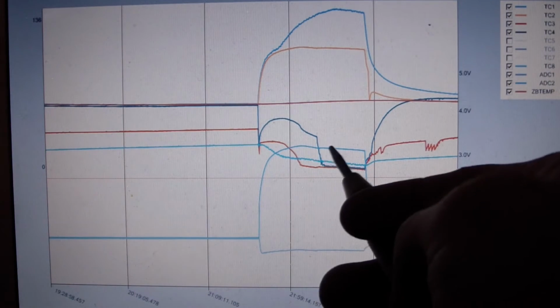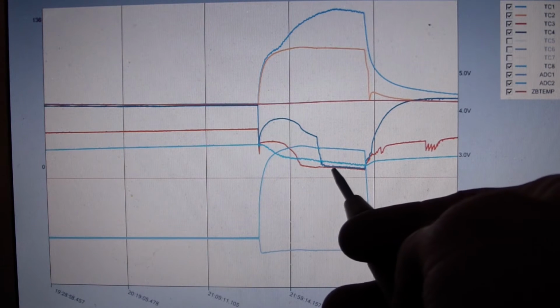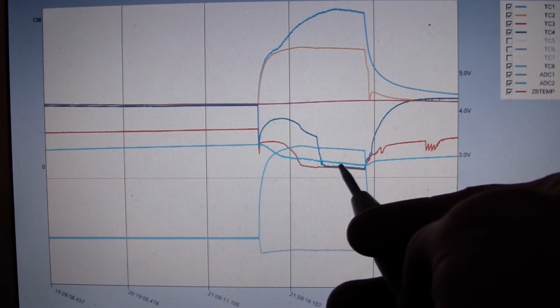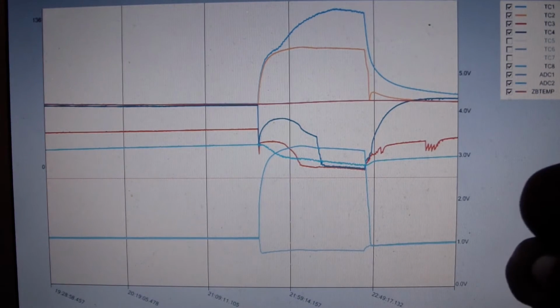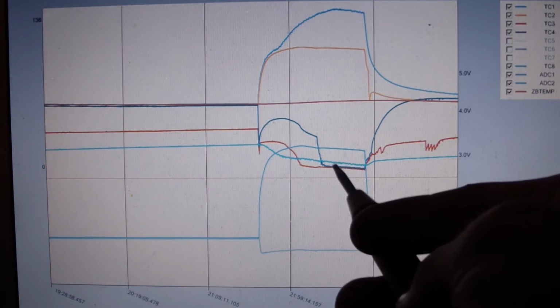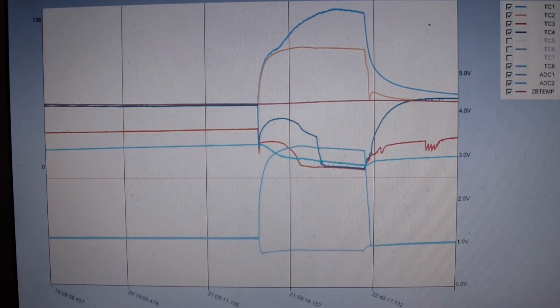Beyond that point, even with the heat interchanger, suction superheat before the compressor is still only 1 to 3 degrees higher than saturation. So we're doing pretty well there. In all likelihood, we're actually passing some liquid through that heat interchanger, which is being flashed off by the heat interchanger.